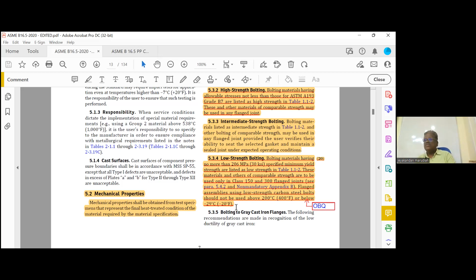Low strength bolting metal having no more than 30 KSI specified minimum yield strength are listed as low strength. These metals and others of comparable strength are to be used only in class 150 and 300 flange joints. Carbon steel bolts should not be used above 400 degrees or below -20. That is an open book question. So if it is a low strength bolt, it should be used only in class 150 and 300 flanges. The temperature limit is not more than 400, not less than -20. That is all open book question.